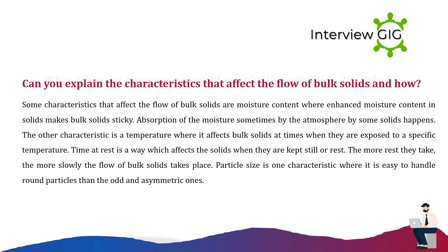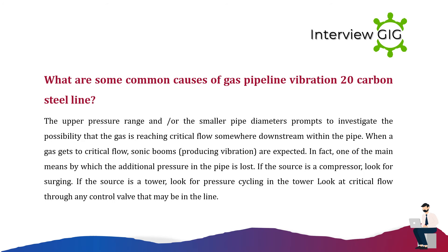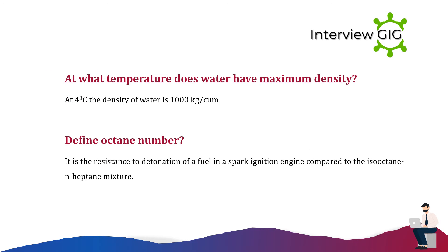What are some common causes of gas pipeline vibration? In a 20-carbon steel line, upper pressure ranges and/or smaller pipe diameters prompt investigation into whether the gas is reaching critical flow somewhere downstream. When a gas reaches critical flow, sonic booms producing vibration are expected — one of the main means by which additional pressure in the pipe is lost. If the source is a compressor, look for surging. If the source is a tower, look for pressure cycling. Also look at critical flow through any control valve in the line.